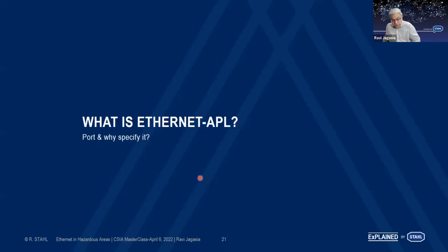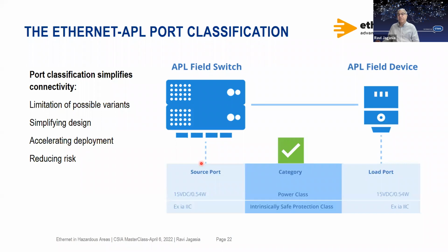We talked about port. Why do we need it? Why specify it? Well, a lot of you may remember intrinsic safety. When we talk about intrinsic safety, we talk about the field device, which is the intrinsically safe apparatus. And then we talk about the source or the associated apparatus, which is powering the intrinsically safe field device. And remember, at that time, we used to check what is called operational power. Is there enough power coming out of this power source to be able to load and provide power for the field device to work effectively?